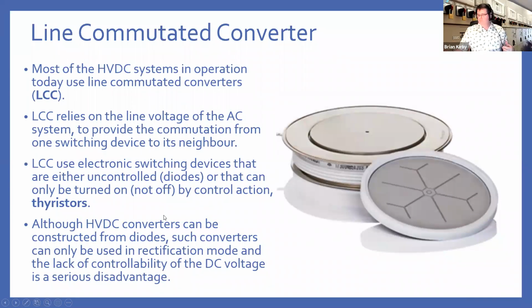There are 2 main flavors of HVDC in operation. Line commutated converters, LCC. They use the AC network to do the commutation, which means that the switching forms a loop through the AC in order to achieve your waveform. It can be achieved using diodes, but that's not really practical for large high voltage systems. Typically they're done with thyristors, which have the advantage over diodes in that you can control when they're turned on, which allows you to control voltage levels. Although you can't turn a thyristor off once it's energized, you have to wait for the AC side to go to 0 to de-energize the thyristor.